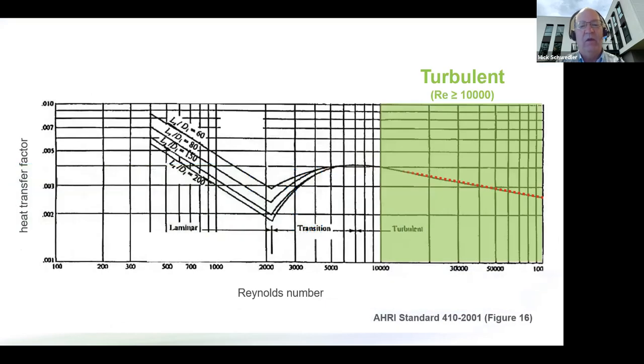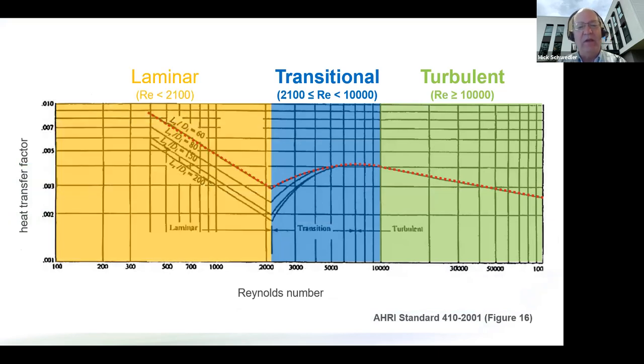What was different? Well, if we go back to heat transfer, we want to stay out of this transitional area. If we remember, we talked about Reynolds number in heat transfer and having a high Reynolds number to promote good heat transfer. Well, in this case, we happen to be in this transitional area. And in this transitional area, the heat transfer goes down and we get that reduced delta T, so we have to reduce the chilled water temperature a lot. Now, one of the things that's kind of surprising is once we get through the transitional region to laminar flow, and what we learned in our textbooks was laminar is bad, actually, when we get into laminar flow, the heat transfer capabilities start to go back up.